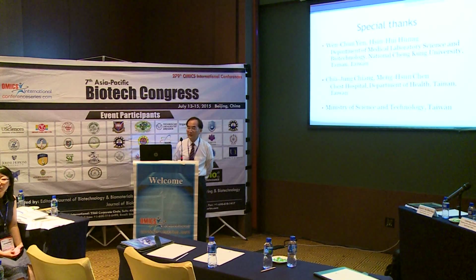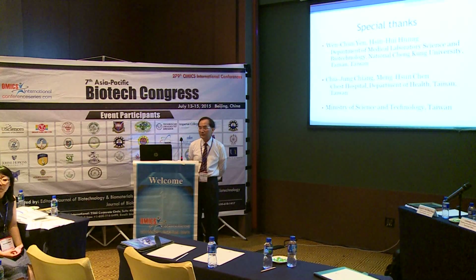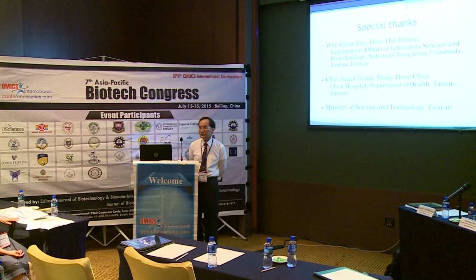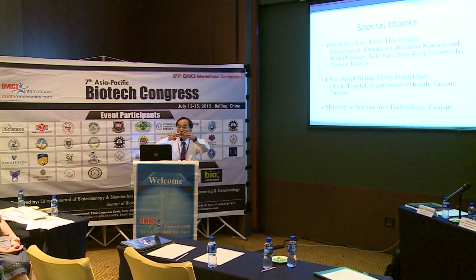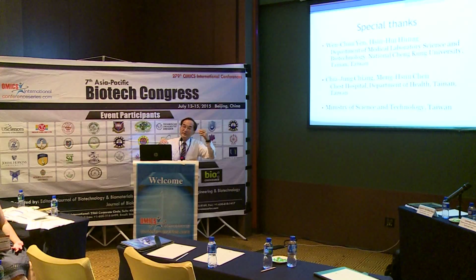For example, as a technician with no expertise, how to detect this? How to interpret the result? They have some special camera because there are many spots, many results. Oh, you can read by your eyes, but we have a small reader. It is a small camera, a CCD camera, and we have a software. I won't talk about it today. It is a simple camera, and it detects the grayscale of each spot, and the software will compare and read the result, and it will output in 2 or 3 seconds.